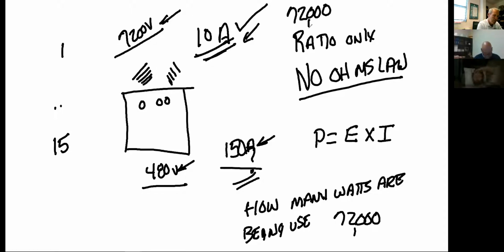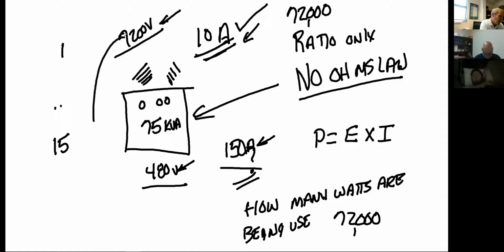They both work. What size transformer should be here? It goes 25, 50, 75. 75 kVA. There you go. So you see how everything kind of factors in, you just got to know the timing of when to use what. My question started out with, I need the ratio, 7,200 to 480. You got it. I gave you an amperage, you got that. Then I asked you for a wattage, then you got that.